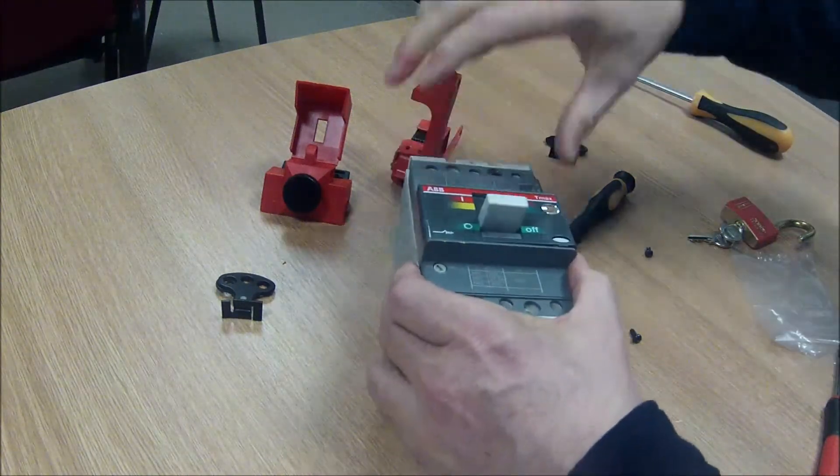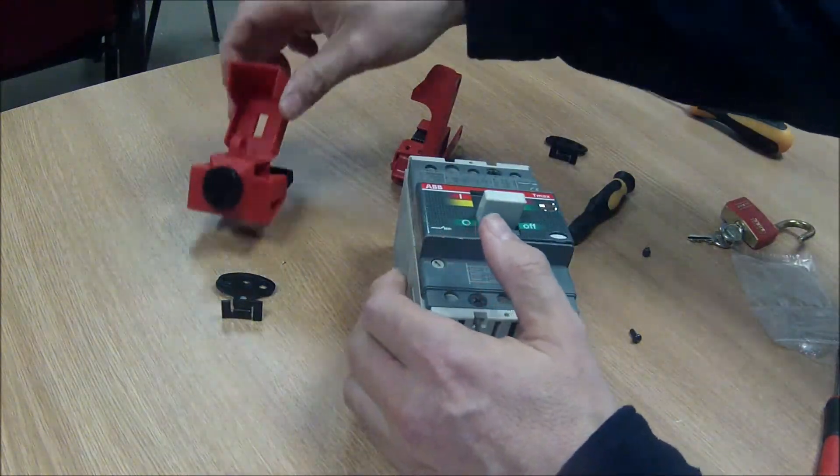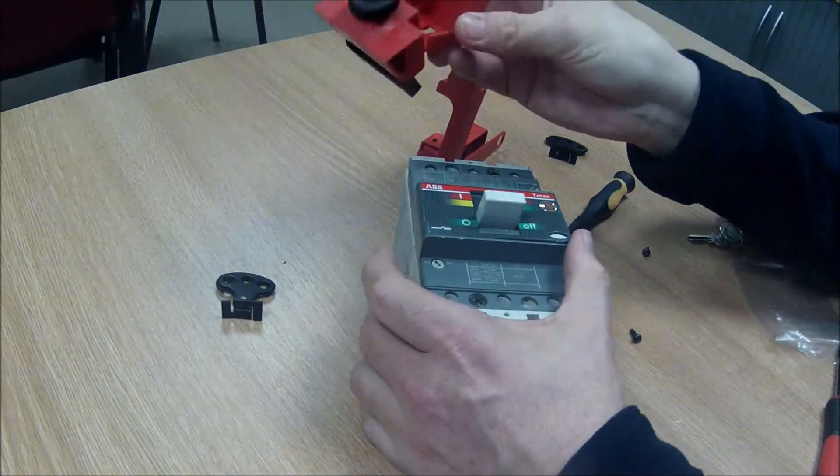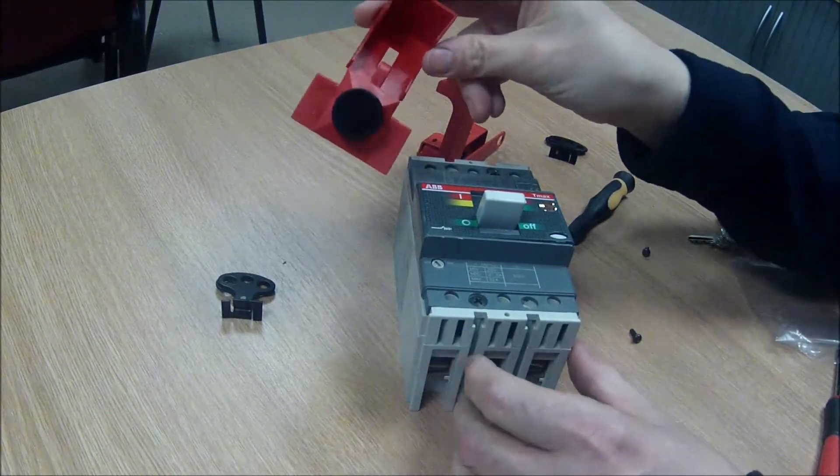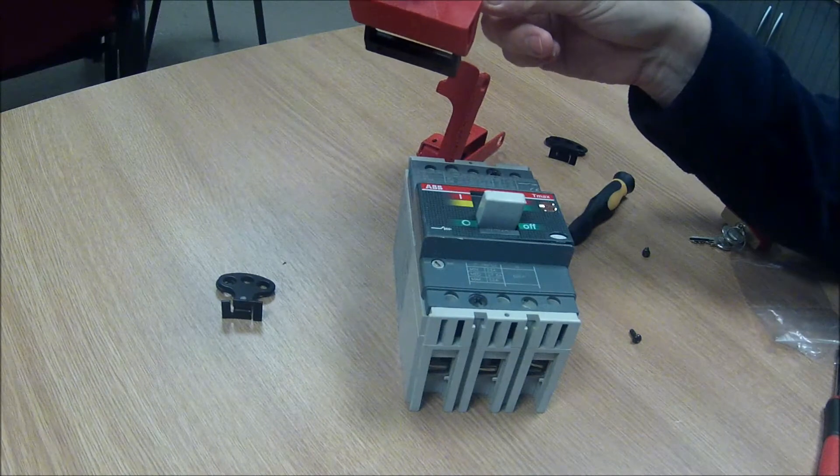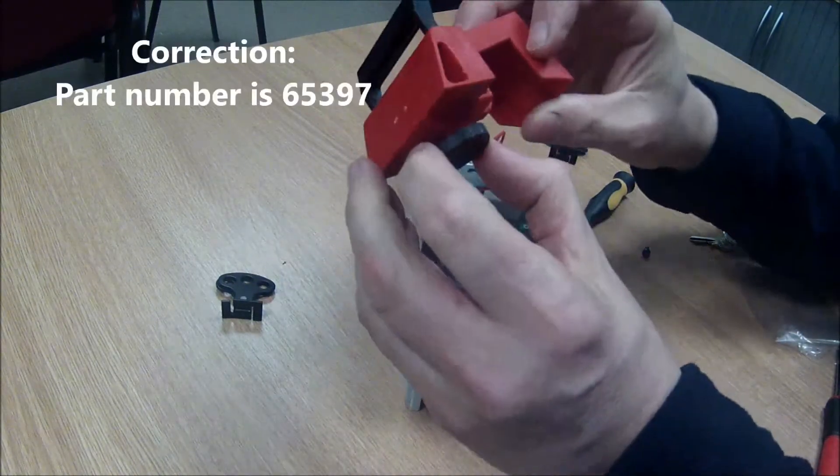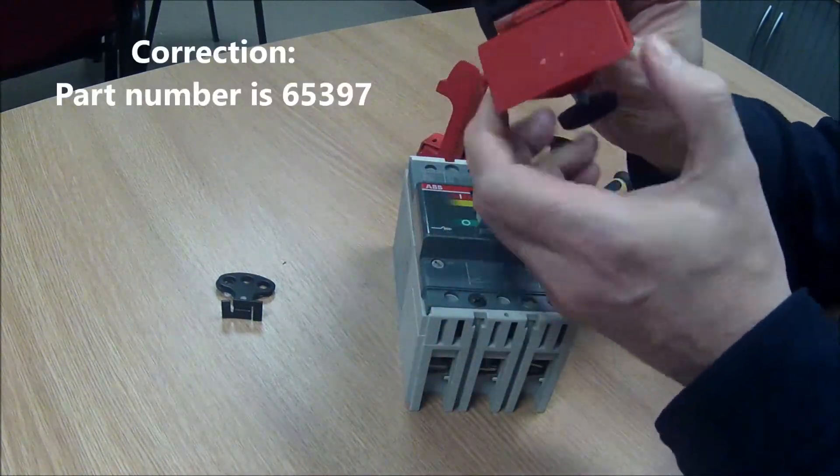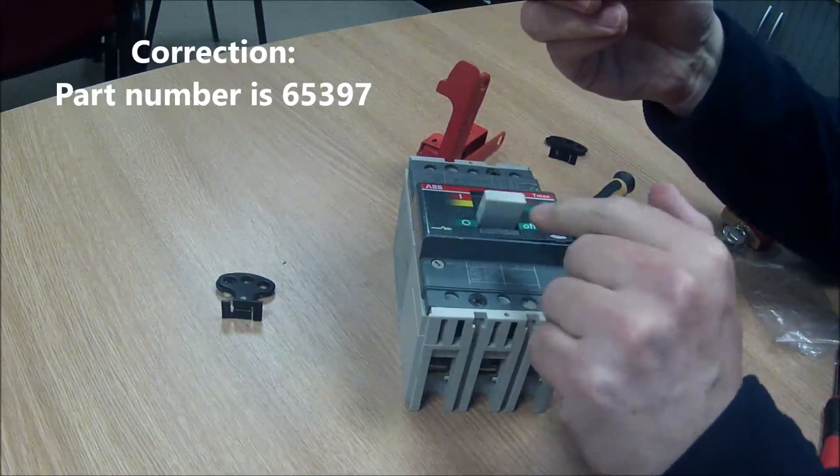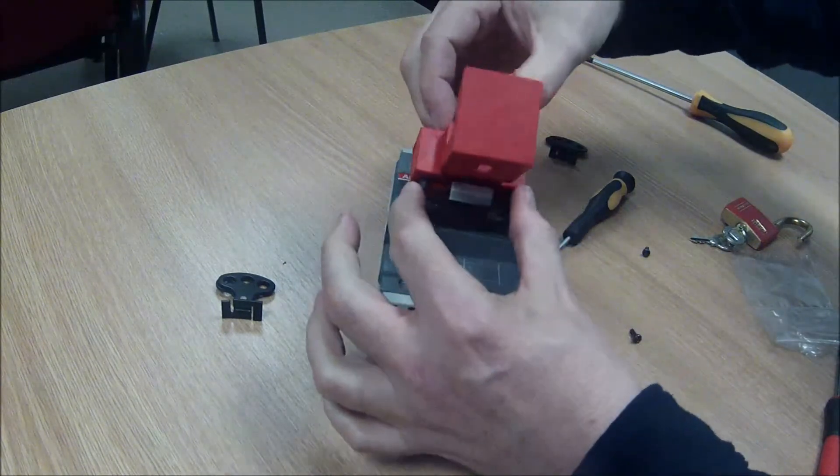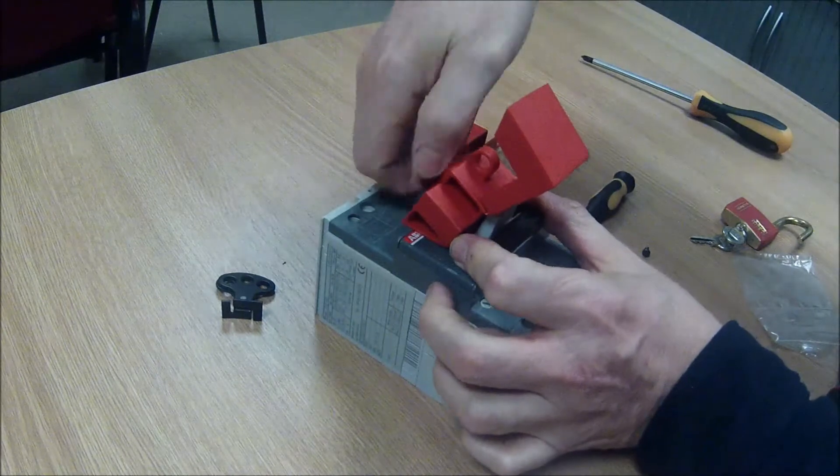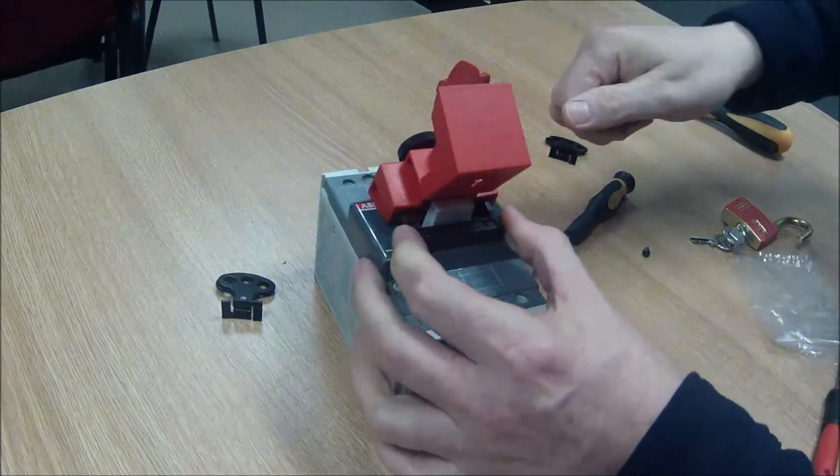We've got two other lockout devices here. One from Brady, one from Master Lock. This is referred to as a clamp on circuit breaker lockout. Part number of this one is 65396. It's got a thumb screw mechanism here. And an opening here through which the toggle of the switch goes. Offer it off onto the toggle like that. Tighten up the thumb screw until it grips. It's now gripping.